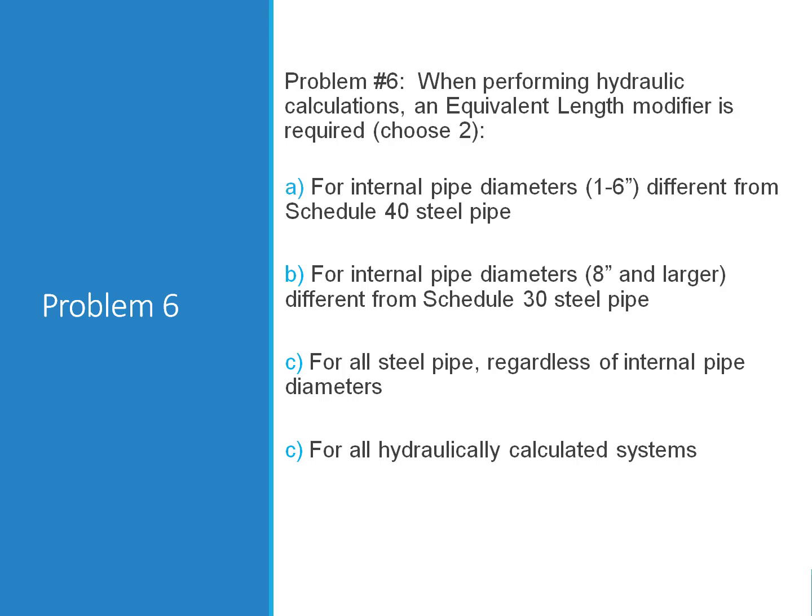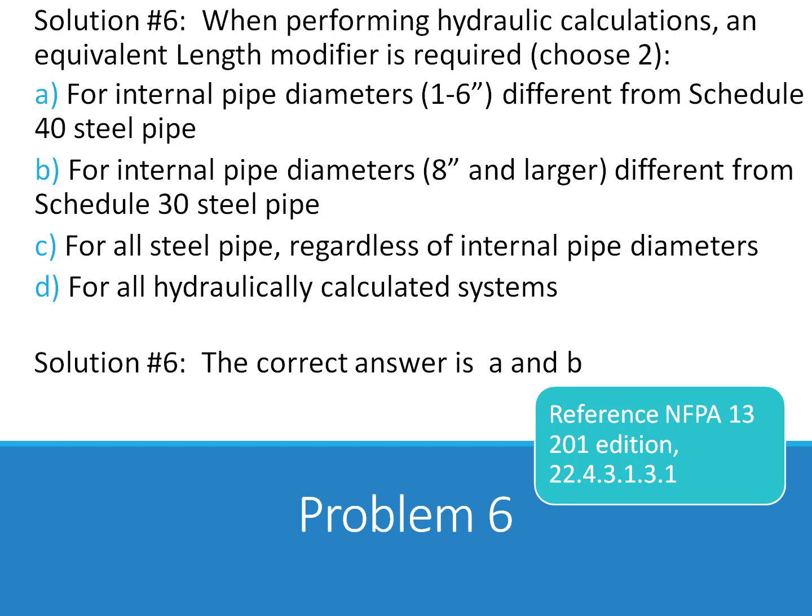For internal pipe diameters 1 inch through 6 inch different from Schedule 40 steel pipe. B, for internal pipe diameters 8 inch and larger different from Schedule 30 steel pipe. C, for all steel pipe regardless of internal pipe diameters. Or D, for all hydraulically calculated systems. The solution to problem number 6 is both A and B.